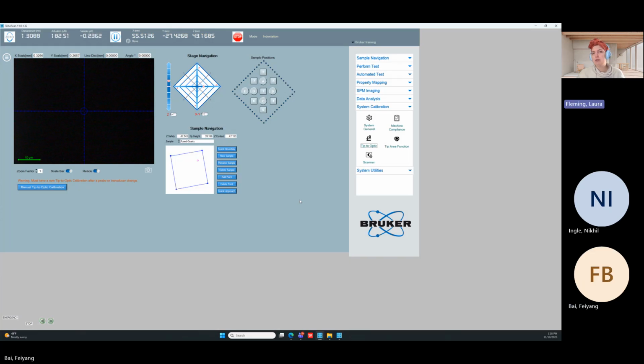Right, so in the equations, hardness is the maximum force divided by the contact area. Reduced modulus is the stiffness divided by the contact area, or the square root of it. Contact area. Do we remember what contact area is? So contact area is how much of the probe is in contact with the sample at the time of the indent, correct? Yes. So the tip area function gives us the relationship between contact depth and contact area. Okay. So normally that needs to be done so that when we do an indent into one of our samples and ask the system to calculate reduced modulus and hardness, we know those calculations will be correct. If your contact area is correct, your tip area function is correct, then you will get proper results. What kind of results do you think we're going to get from scratch testing? What are we looking for if you look at scratch testing?